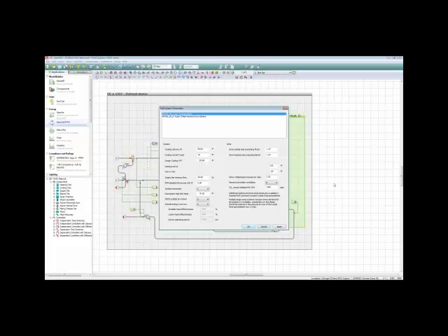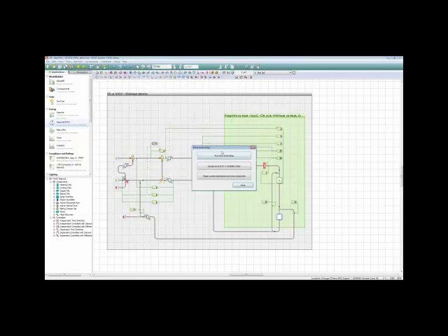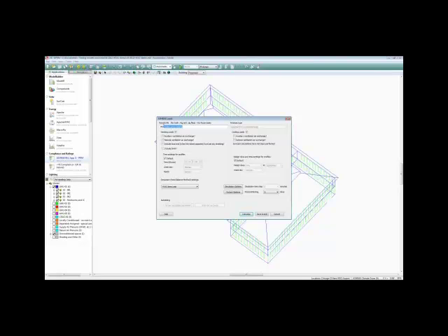And the next step would be to go to the room and zone level sizing. And I'm going to go ahead and just run that to show you what it does. You can see that this is defaulted to the system that I was looking at in Apache HVAC. 5 systems in my project, but this selector has just defaulted to that one. I can run this now for any one of these systems I choose from here. So I don't need a thing called proposed.asp unless I am doing a performance rating method project and I'm using the performance rating method Navigator.